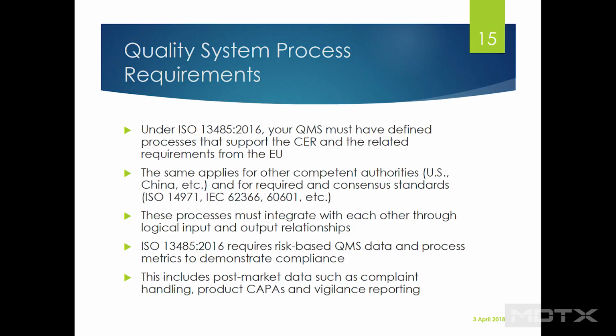Let's see, and this of course includes the post-market data, such as complaint handling, product CAPAs, and vigilance reporting. Those are really key elements that you have to have those processes connected up to your post-market surveillance program, and of course your PMCF, and as well, it has a major role in how you handle and develop your CERs.